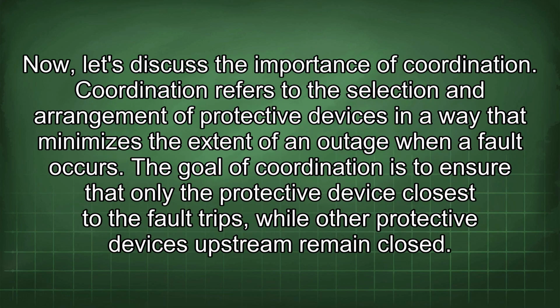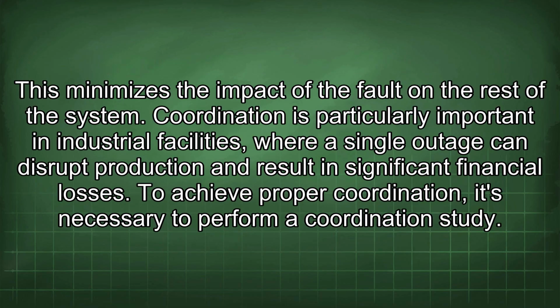Now let's discuss the importance of coordination. Coordination refers to the selection and arrangement of protective devices in a way that minimizes the extent of an outage when a fault occurs. The goal of coordination is to ensure that only the protective device closest to the fault trips, while other protective devices upstream remain closed. This minimizes the impact of the fault on the rest of the system. Coordination is particularly important in industrial facilities where a single outage can disrupt production and result in significant financial losses.